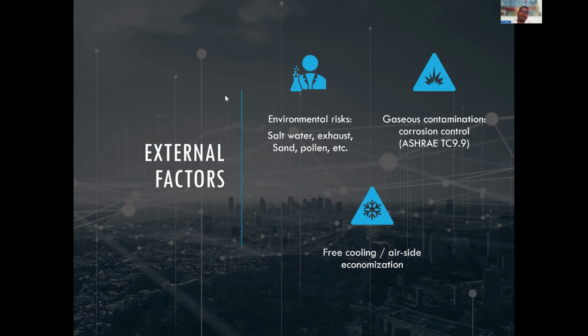If you're a data center in New York City, you're going to have a ton of exhaust fumes. Also, if you're located on the side of the highway, you're going to have a lot of exhaust fumes there. If you're a data center in the desert, you may have to protect against sand getting into your outdoor air units, pollen, etc. So those environmental risks should definitely be accounted for when determining the type of filter that we choose.